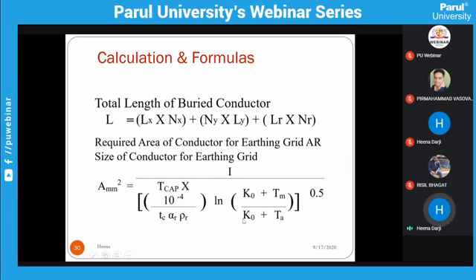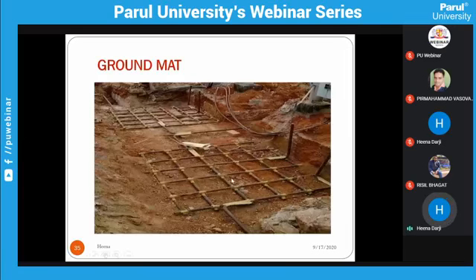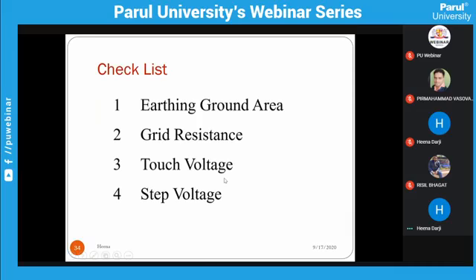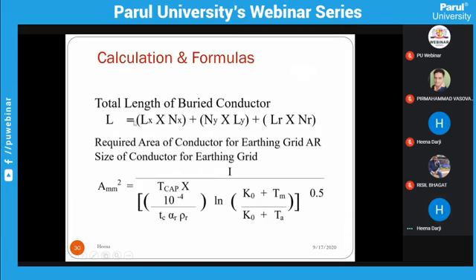Now these are the calculations. Your total length of buried conductor: your substation area is all this, but your earthing material area is like this, in X and Y direction. So L is equal to Lx into Nx plus Ny into Ly plus Lr into Nr. It means required area of ground for the earthing grid, required size of conductor for the earthing grid. So this area is your material area.